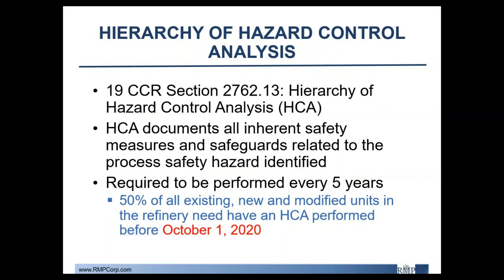An HCA is an independent study that can be performed in tandem with your PHA and SPA or LOPA studies to identify, analyze, and document all inherent safety measures and safeguards to reduce each hazard to the greatest extent feasible. It's beneficial to perform your HCA in conjunction with your PHA or SPA as the same team members are normally required, and HCAs are required every five years — the same cyclical requirements as PHAs. All refineries are required to perform HCAs for 50% of all existing, new, and modified units before October 1, 2020. This includes all units, including utility units such as steam, nitrogen, instrument air, tank farm, and wastewater treatment.